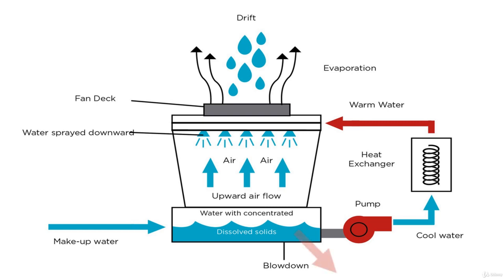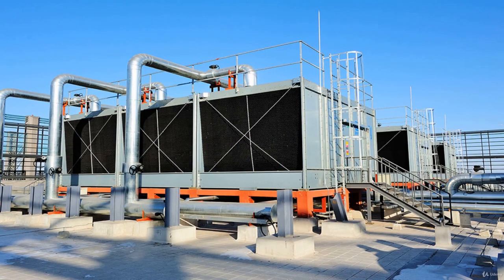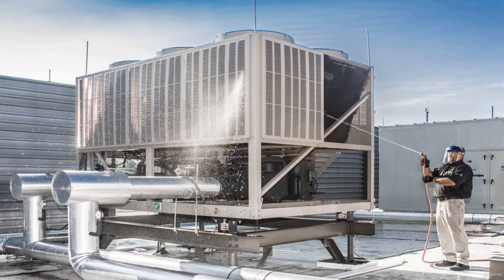To prevent buildup of deposits, cooling tower systems remove a portion of the water through a process called blowdown. Makeup water is then added to replace evaporated losses and blowdown volume. Cooling towers can therefore account for a large portion of a building's total water use. To significantly reduce makeup water inputs, it's important to achieve a target cycles of concentration. Increasing the number of cycles can save thousands of gallons of potable water during a building's peak cooling periods, and chemically analyzing makeup water allows for calculation of optimal cycles.